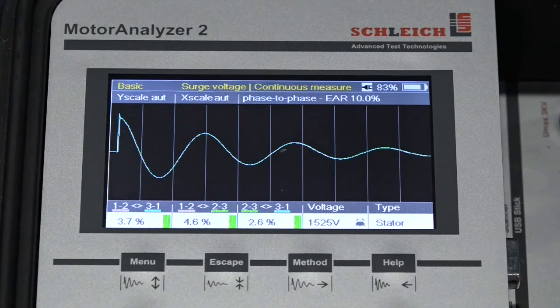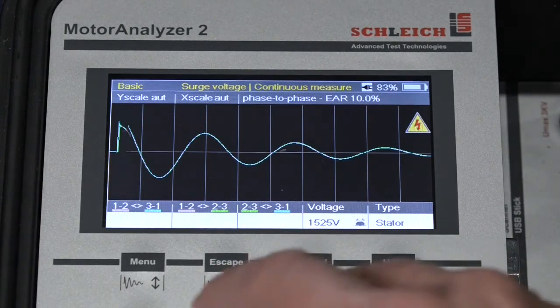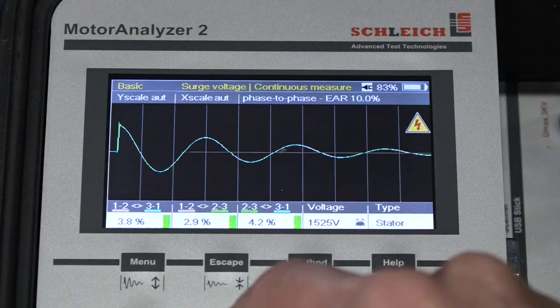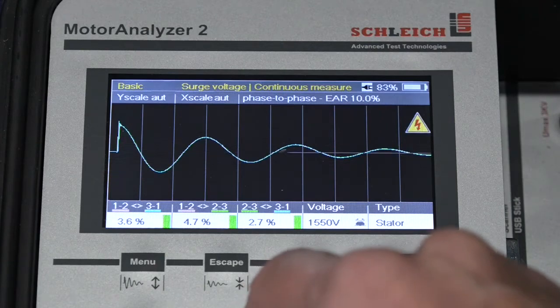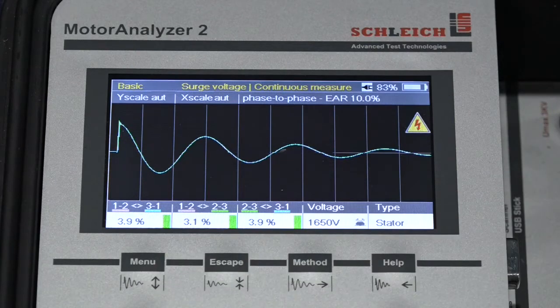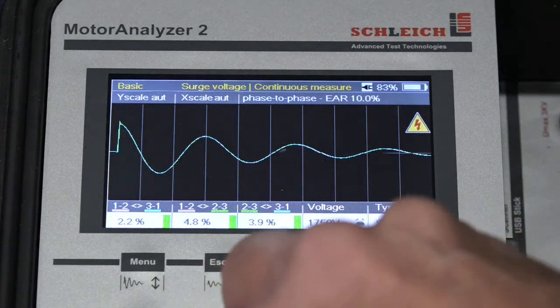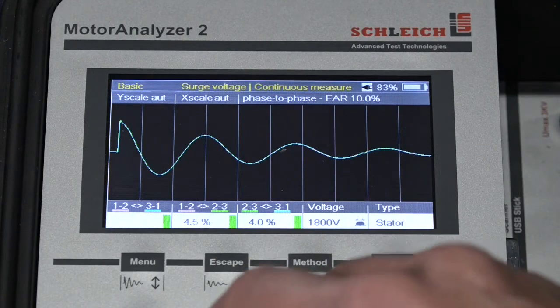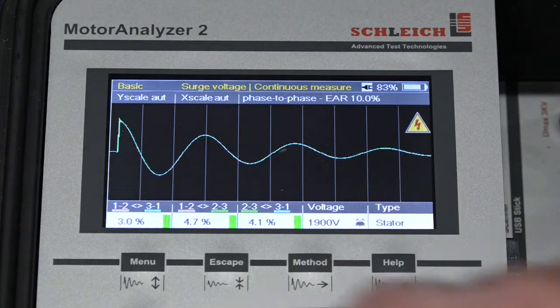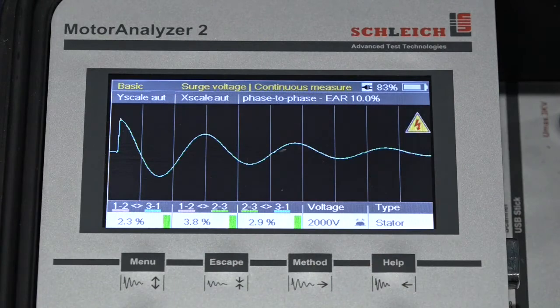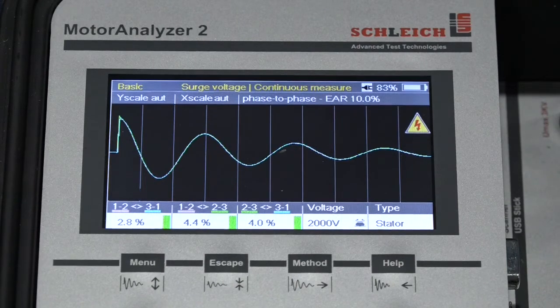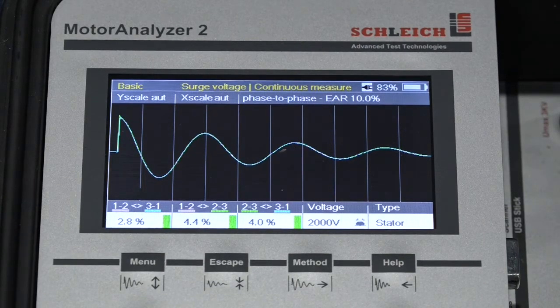So let's just press the start button and do a test. You can see it's applying the test at 1525 there. I can ramp up the voltage with the knob while it's in this mode. And there's a test at 1650. 1800 volts. 1900 volts. And finally 2000 volts. So even though this instrument in its automatic mode behaves differently than other testers out there, we still have the same kind of ability to do what you've done in the past. Press the stop test button to finish.